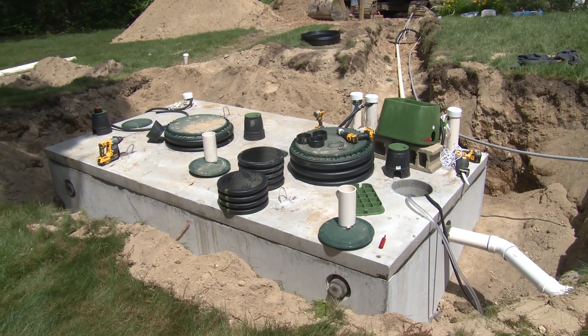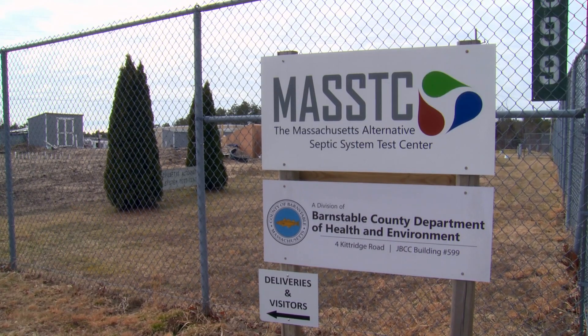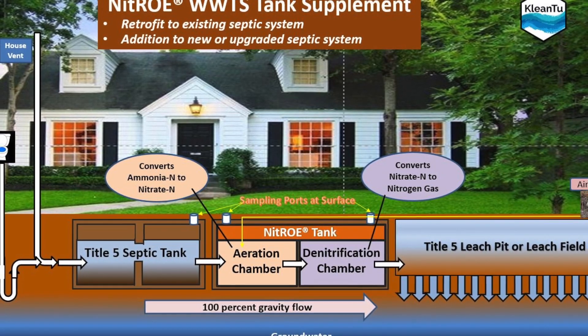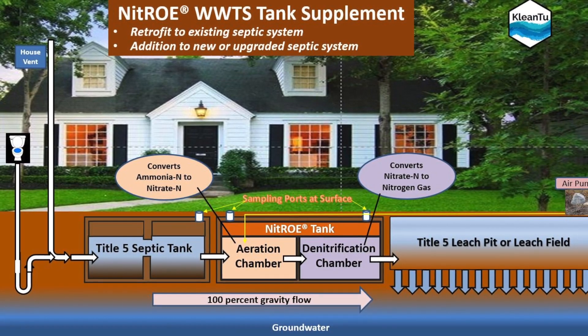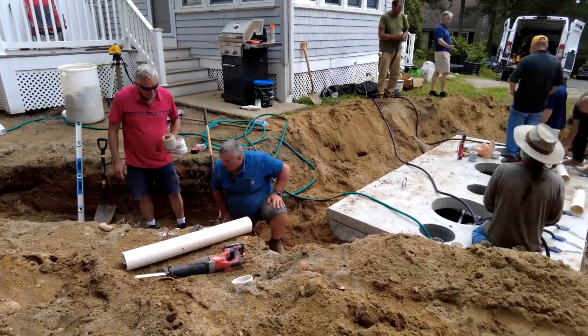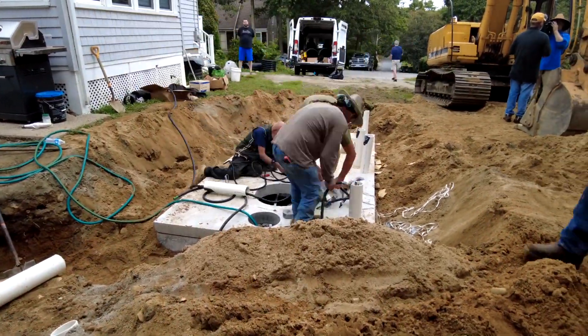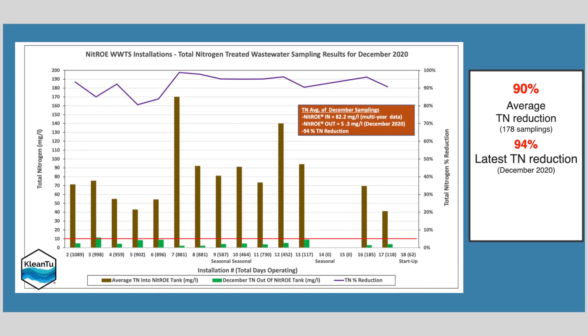What we're installing here with this unit is the result of four to five years of ongoing testing and R&D, both in the field and at the Massachusetts Alternative Test Center. The NitROE tank goes in between the septic tank and the leach field or leach chamber, where it focuses on removing nitrogen, organic carbon, and suspended solids. The specific focus is on removing total nitrogen from the system, and we're expecting this system will achieve 90–95% nitrogen removal consistently.